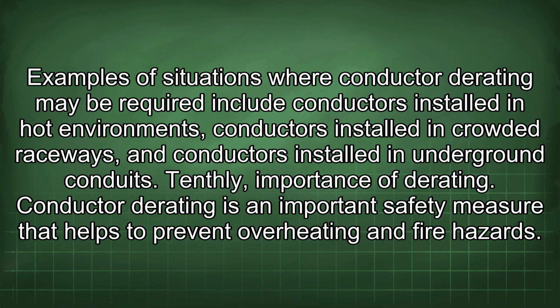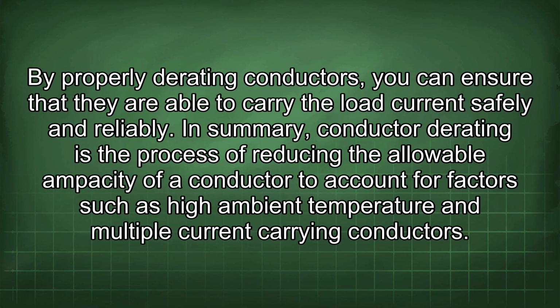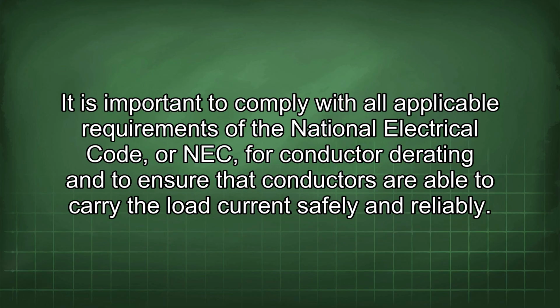Tenthly, importance of derating. Conductor derating is an important safety measure that helps to prevent overheating and fire hazards. By properly derating conductors, you can ensure that they are able to carry the load current safely and reliably. In summary, conductor derating is the process of reducing the allowable ampacity of a conductor to account for factors such as high ambient temperature and multiple current carrying conductors. It is important to comply with all applicable requirements of the National Electrical Code, or NEC, for conductor derating and to ensure that conductors are able to carry the load current safely and reliably.